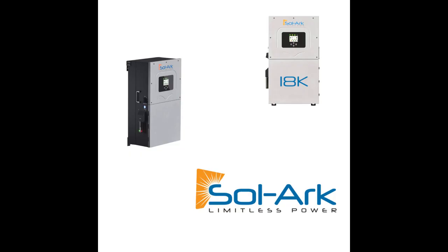So with our high voltage inverters or commercial inverters, which Mark already referenced, we have a 30 kilowatt 120/208 volt three-phase inverter, and then a 60 kilowatt 277/480 volt inverter. With our Sol-Ark batteries, we have two specific indoor models, and each one is designed to pair with a specific inverter, and that really comes down to the voltage range of the inverter and why we have the different sizes, right? So we have a 40 kilowatt hour stack that pairs with the 30K, and a 60 kilowatt hour stack that pairs with the 60K inverter.